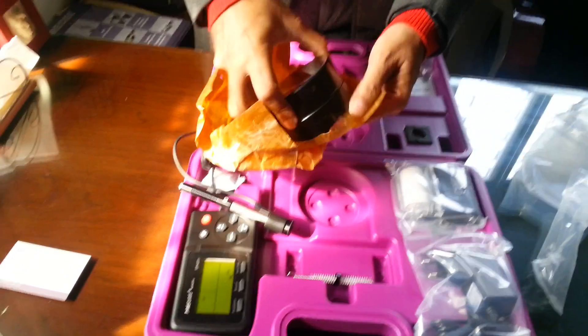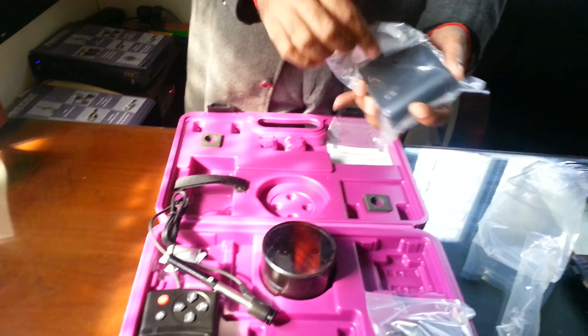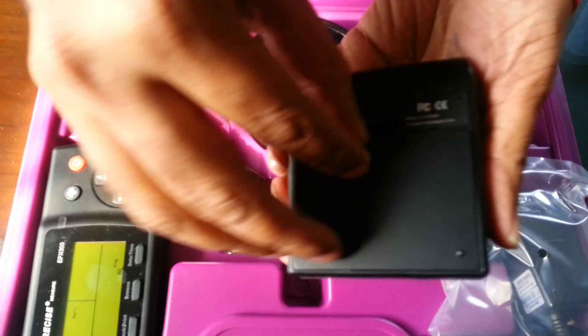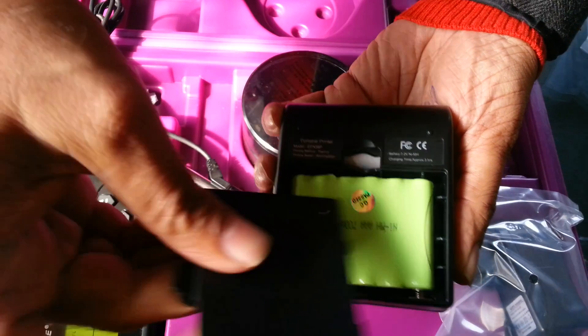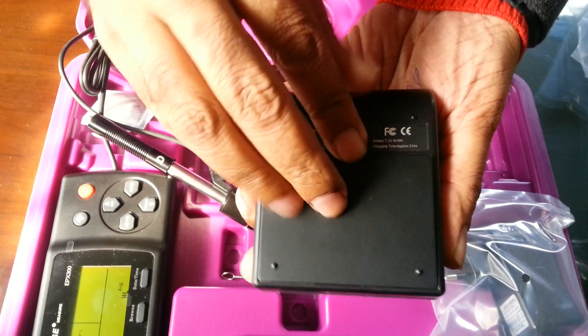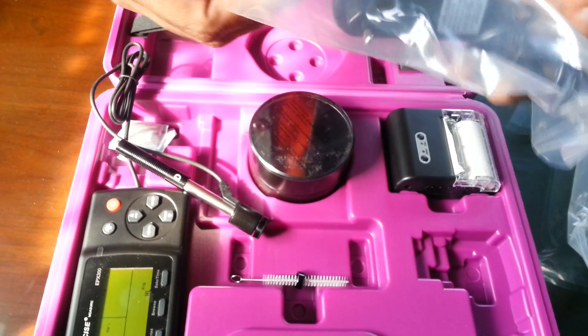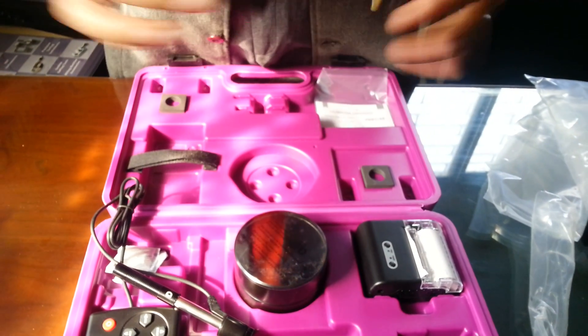This is the test block to check and calibrate our instrument. This is the only hardness tester which comes with a wireless printer. It has a feed button and a power button, and it comes with a rechargeable 7.2V lithium battery. Having this wireless printer saves on human error, and you can take readings of one particular product — as many as nine readings — and take a printout.